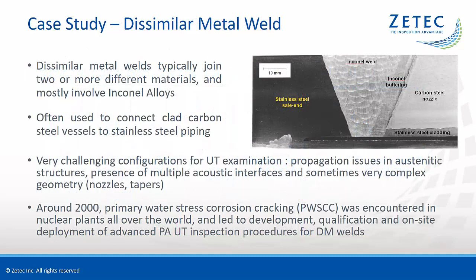The last case study is about inspection of dissimilar metal welds, or DM welds. These welds typically join two or more different materials and mostly involve Inconel alloys. They are often used to connect internally clad carbon steel vessels to stainless steel piping. Dissimilar metal welds are very challenging configurations for UT examination due to the various propagation issues in austenitic structures, the presence of multiple acoustic interfaces, and sometimes very complex geometry including conical nozzles and tapers.